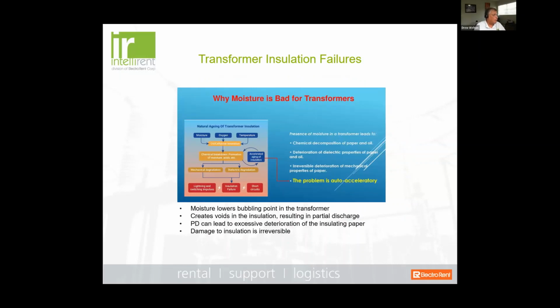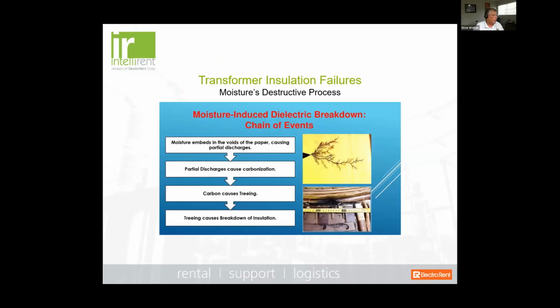Well, why is moisture bad? Well, moisture basically lowers the bubbling point in the transformer. And this will create voids in the insulation and eventually lead to partial discharge. And the PD, again, can lead to excessive deterioration of the insulating paper, and the damage to the insulation is irreversible. And this is important to know. It's important to get a good assessment in terms of your moisture content in the insulation so that you can take corrective action before it gets worse.